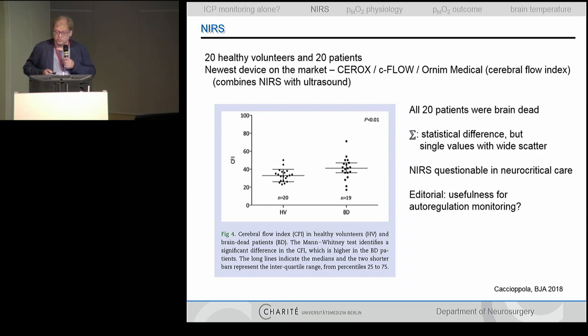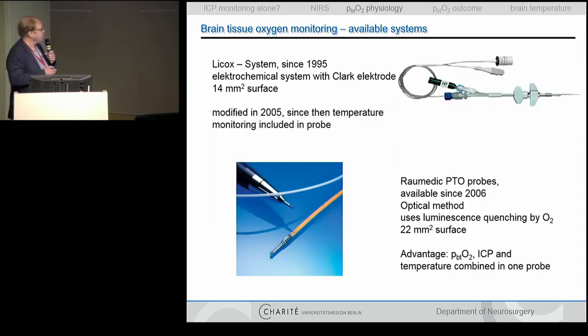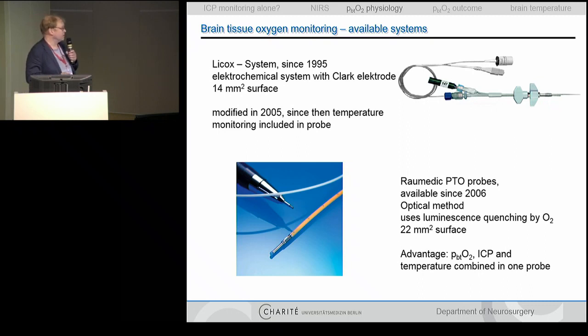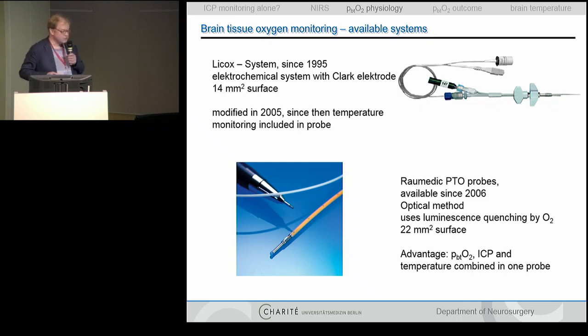But there's another technology shown before: the Licox system and the Raumedic PbtO2 probes — both measure brain tissue oxygenation. These are the two available systems on the market, established maybe 25 years ago. The Licox system is electrochemical, with most of the world's research published using it; a temperature probe was later included in the same probe. The Raumedic probe came on the market one decade later. In clinical practice they show comparable values. The advantage of the PbtO2 probe may be that ICP, temperature, and oxygen are combined in one probe.